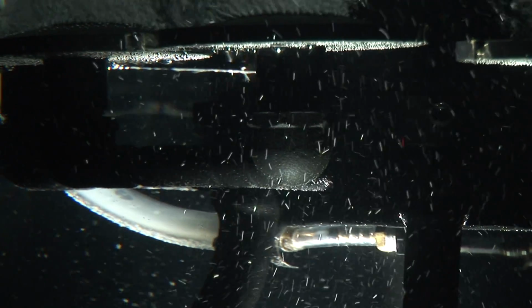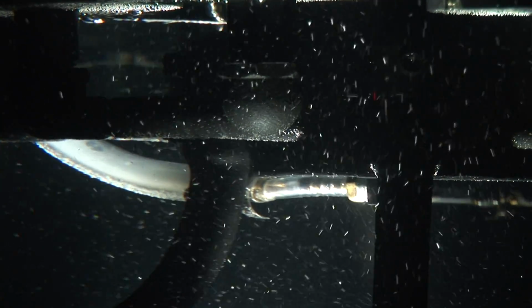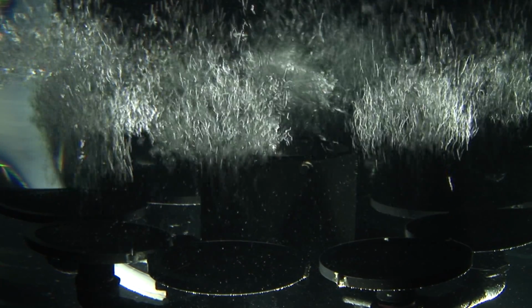Mars is diffused aeration technology, which uses a combination of large bubble, which comes from a static tube, which is an effective mixing, and it also uses fine bubble, which is efficient for oxygen transfer. The Mars unit utilizes fine bubble technology, which is simply very small air bubbles. A lot of aerators use coarse bubble, where the bubbles are larger. The coarse bubble aerator is good for mixing because it stirs the water up. You get a lot of movement. The fine bubble, though, is much more efficient for oxygen transfer. Now, the Mars unit uses both fine bubble and coarse bubble.